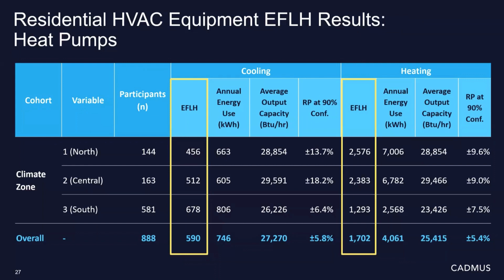The output capacity for heat pumps was also much lower than gas equipment, and heat pumps are generally sized for cooling with some exceptions. Note that these results do reflect the average heat pump customers, not necessarily customers who are planning to use their heat pump systems as their primary heating system. Without any sort of customer survey or supplemental data, we do not know what percent of the heating load these units actually served. But in all of the climate zones, we did achieve less than 10% precision at a 90% confidence interval for the heating EFLH results.